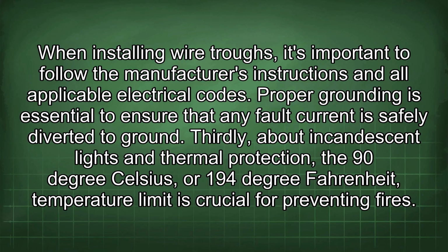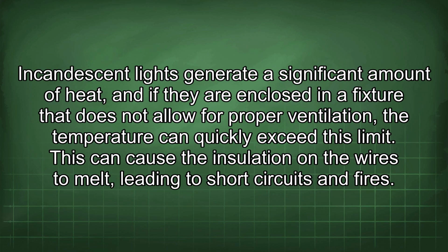Thirdly, about incandescent lights and thermal protection, the 90 degrees Celsius or 194 degrees Fahrenheit temperature limit is crucial for preventing fires. Incandescent lights generate a significant amount of heat, and if they are enclosed in a fixture that does not allow for proper ventilation, the temperature can quickly exceed this limit. This can cause the insulation on the wires to melt, leading to short circuits and fires.